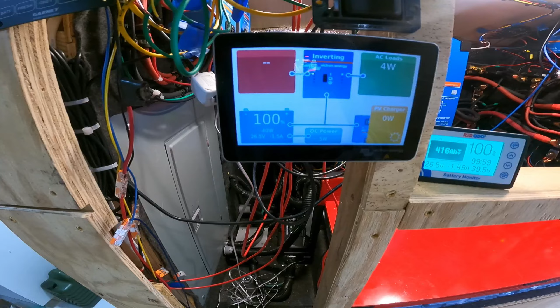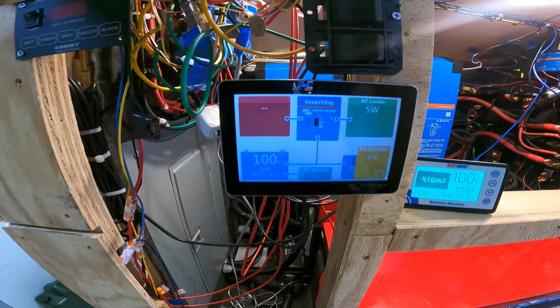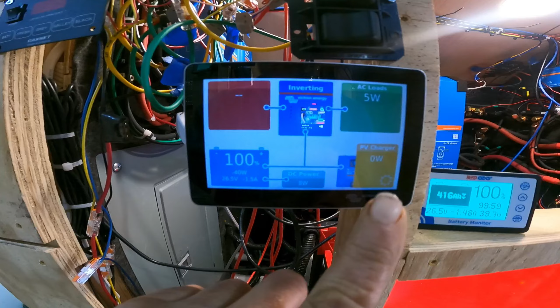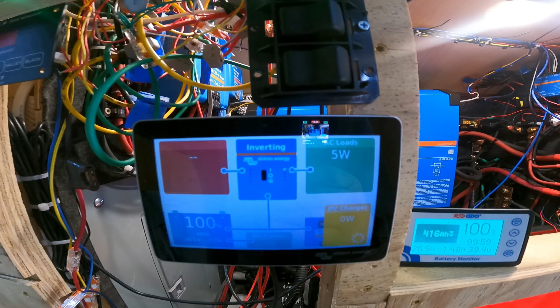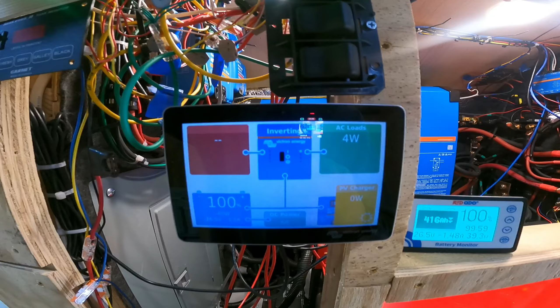Right now we're on the 24 volt side, the Cerbo GX. I changed it back to the classic UI so I could more effectively show you the difference. As you can see, my inverter is on and shows that it's inverting. It's showing a total of 4 or 5 watts of AC load, which I assume is the internal power consumption of the inverter, because every electrical breaker in my panel is off. There are no external loads on that inverter whatsoever, so that has to be AC load from inside the inverter, not external.